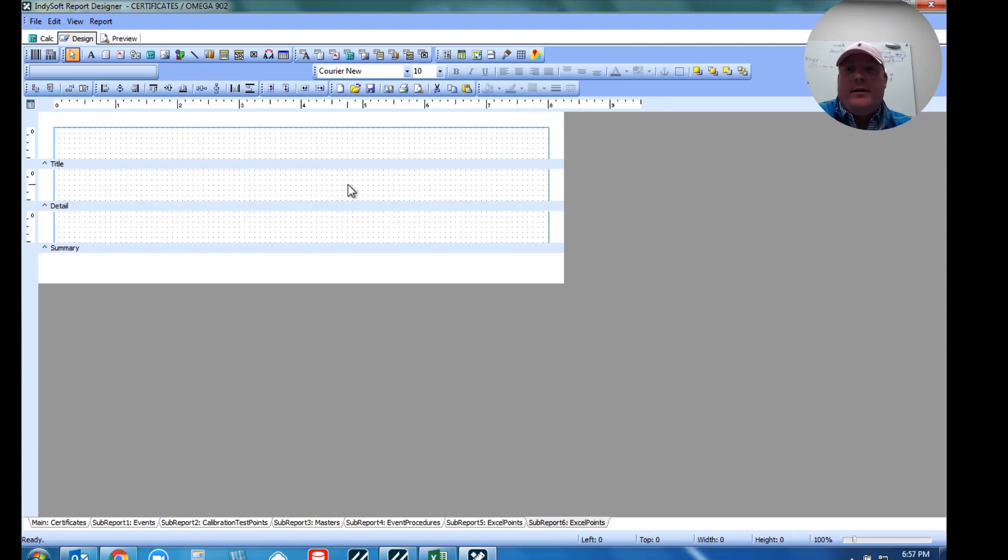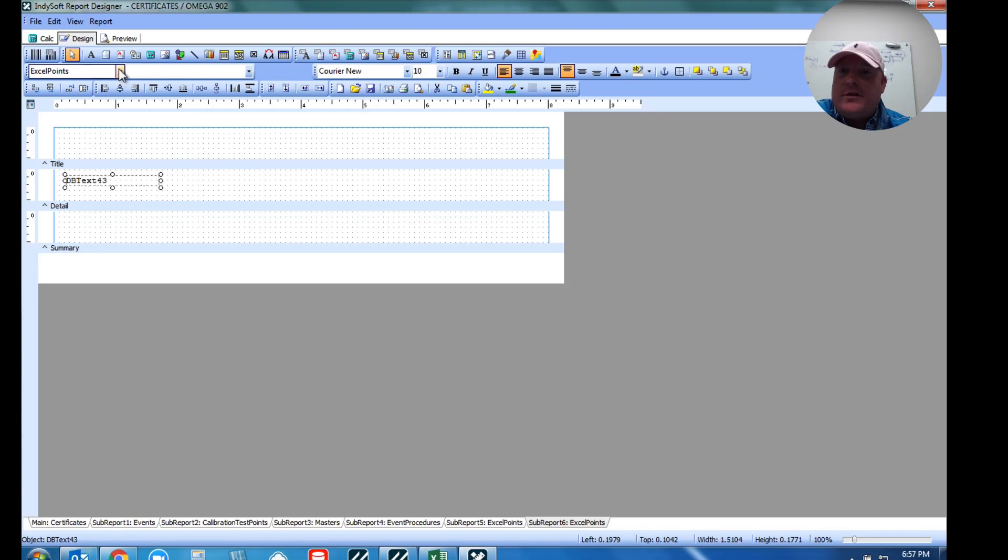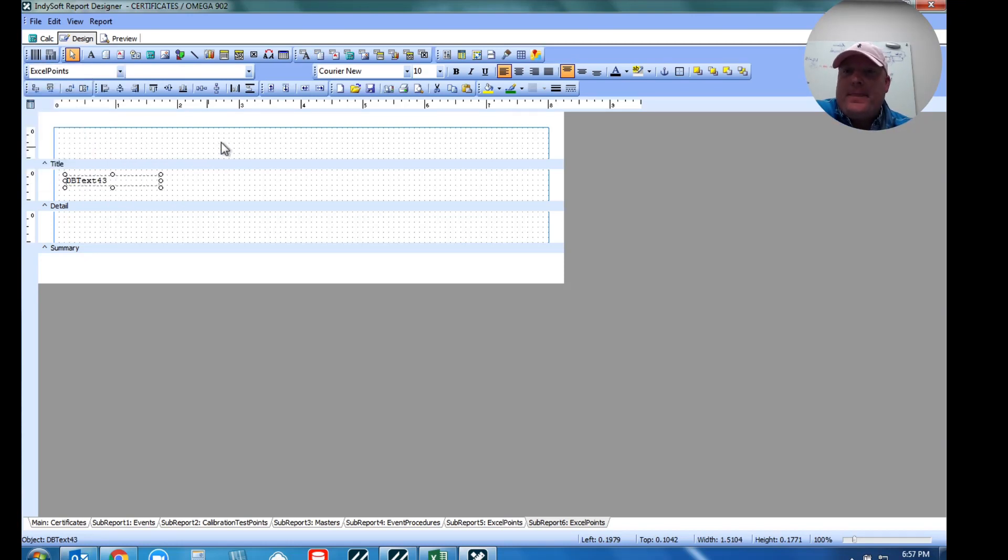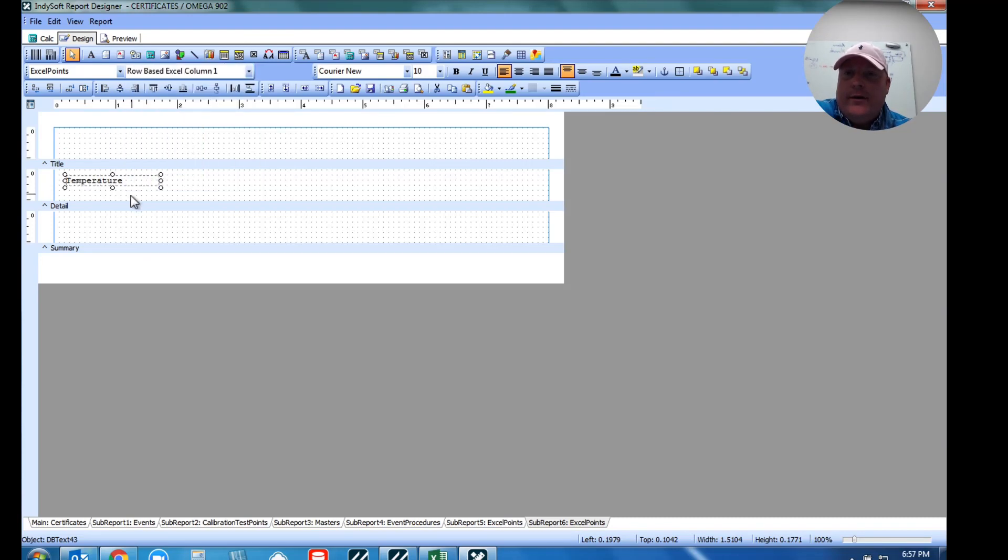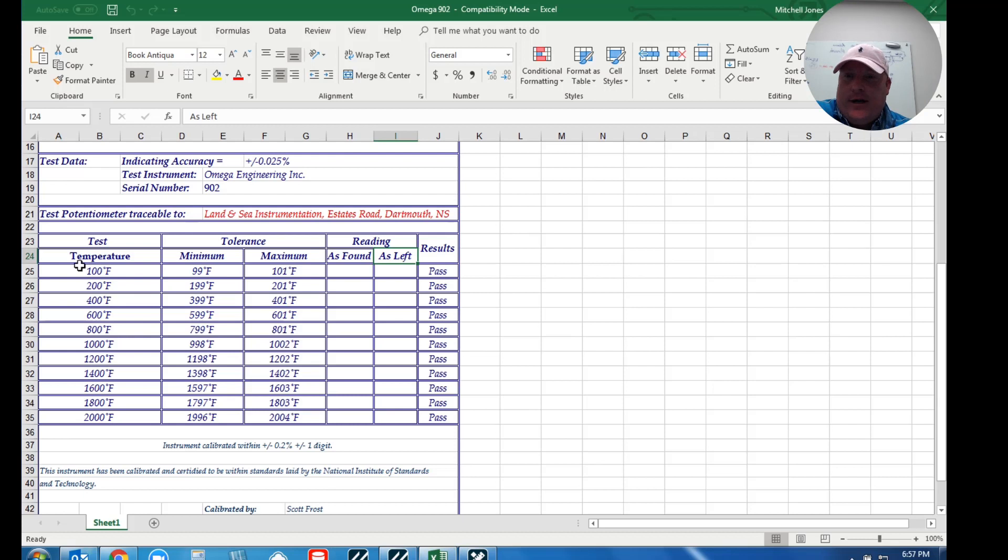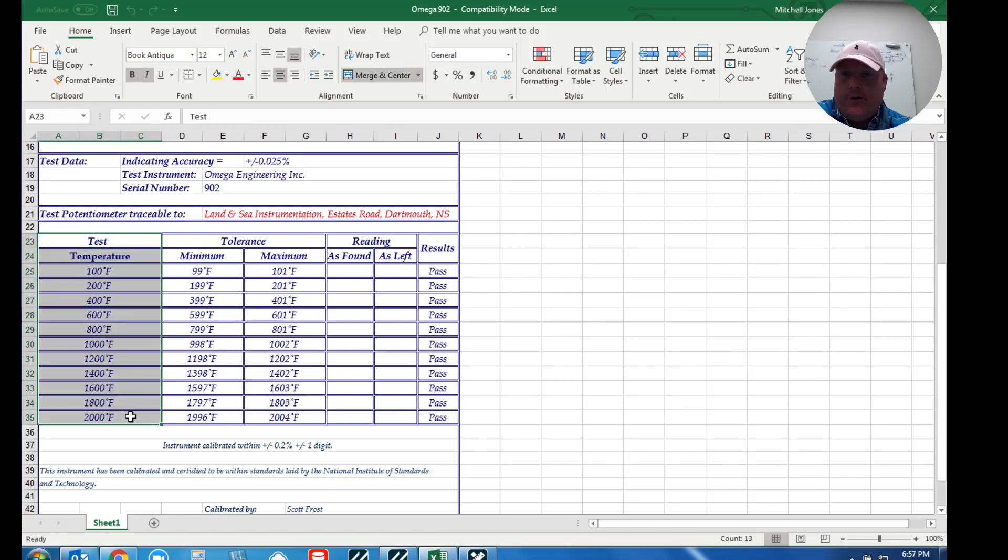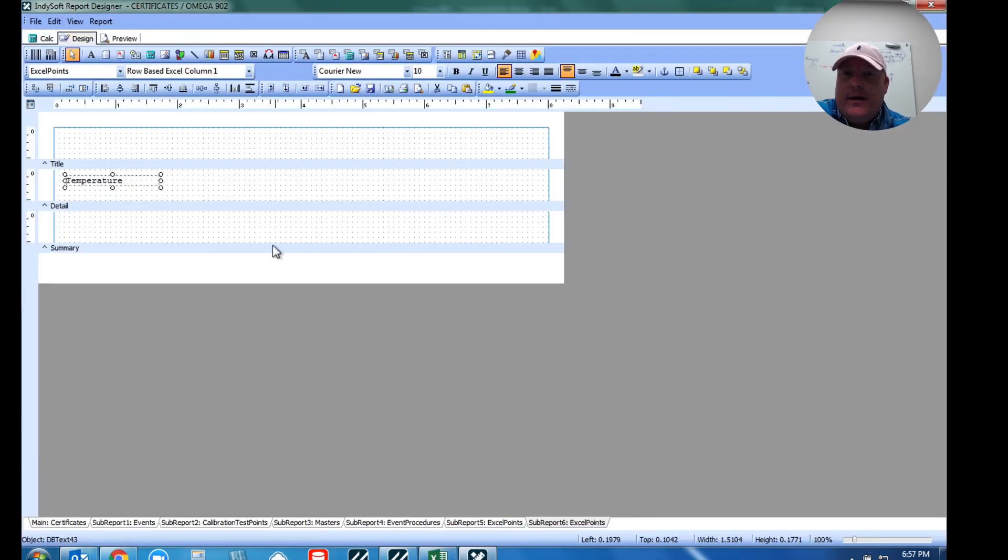But you'll notice it says no data pipeline assigned. So the first thing we want to do is actually assign our Excel points. That's those Excel points that we've specified back on the equipment screen. So I'm going to choose that. And like any other data report that we add in, we typically do want to have a shift rule set up inside of here. So I'm just going to shift these test points to where they show up after sub report five. So then we simply just navigate over to sub report six. And in the detail band we start dropping in our database pipeline fields. But you'll notice it's kind of pre-configured to look at the Excel point table.